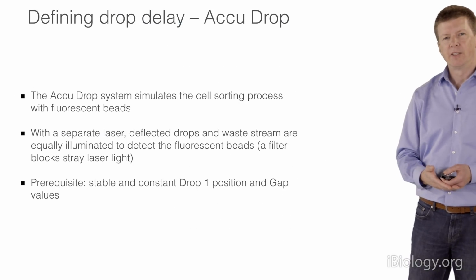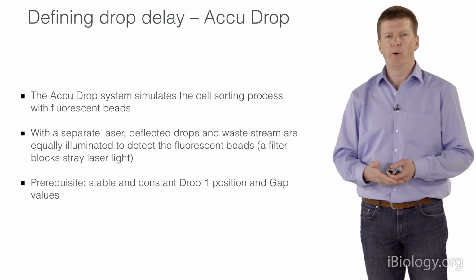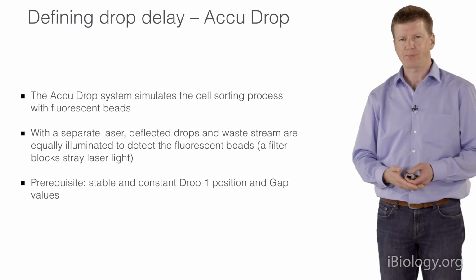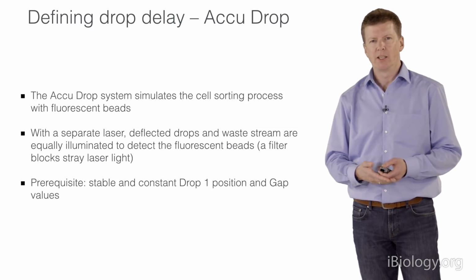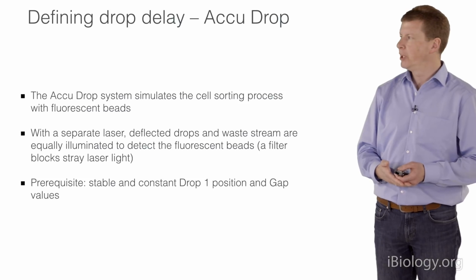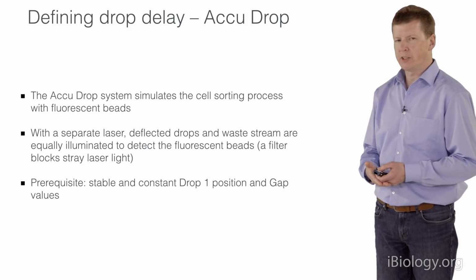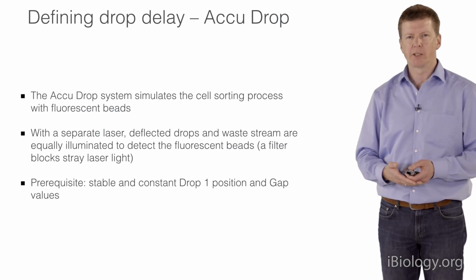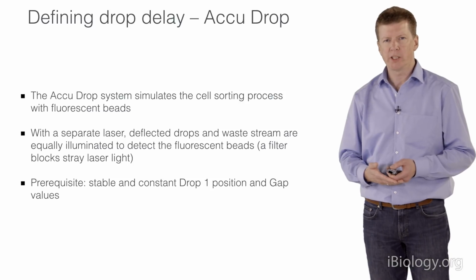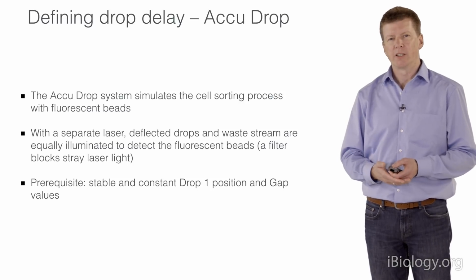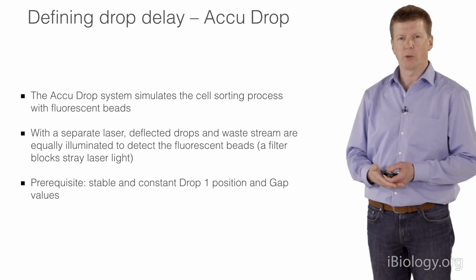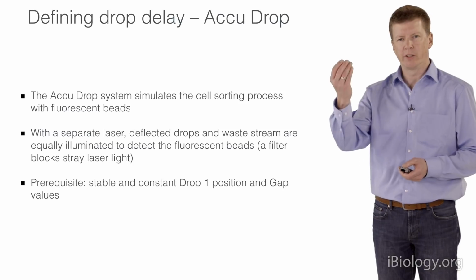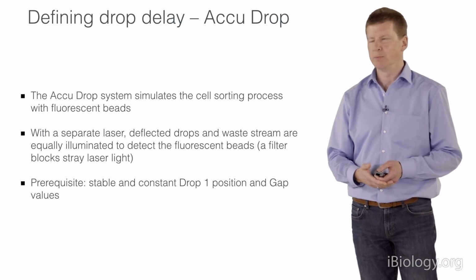To define the drop delay, there are different systems available. The most prominent one is the so-called AccuDrop system. This consists of a separate laser which is equally illuminating the deflected drops and the waste stream. So when we are now using fluorescent beads, we can simulate the sorting process, and when we have calculated the right drop delay for sorting, all the beads should be sorted out and no bead should be left in the waste stream.